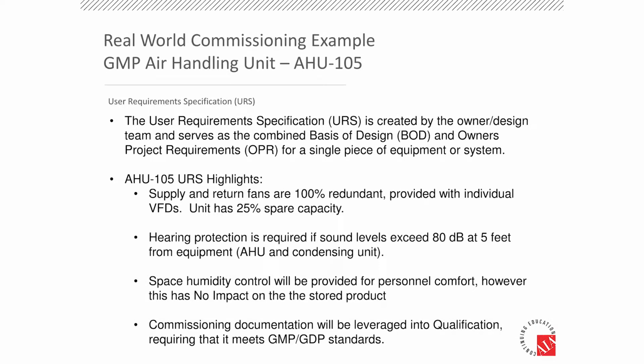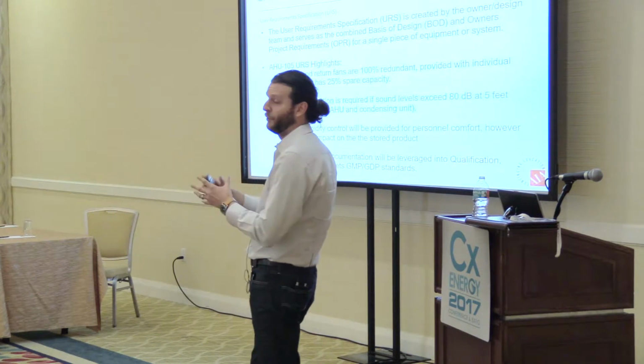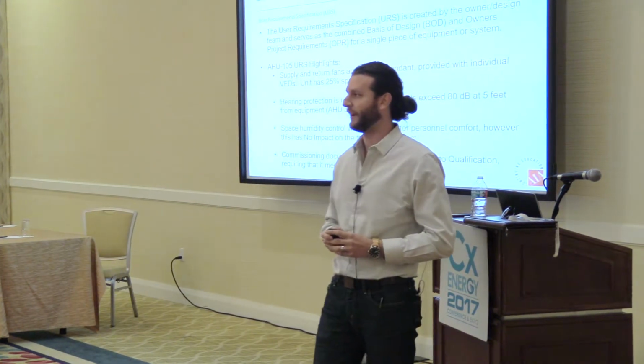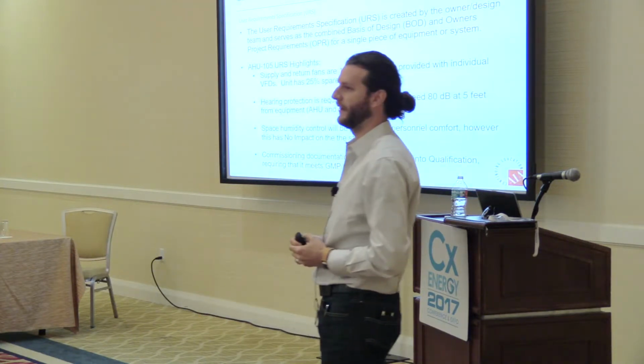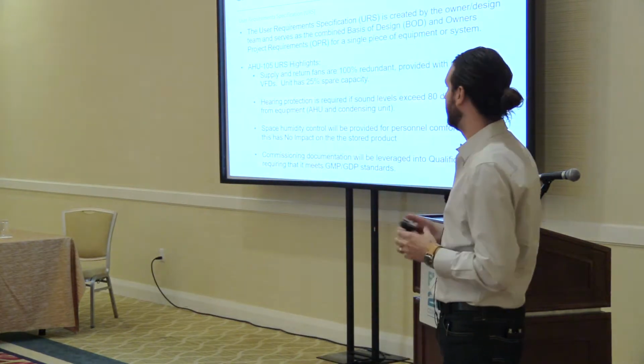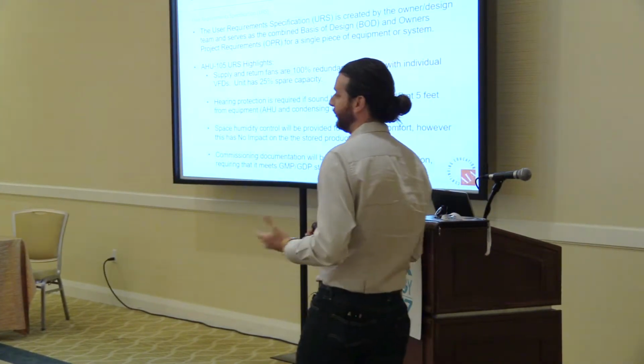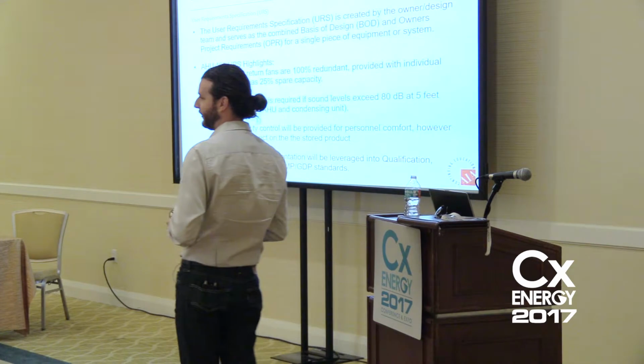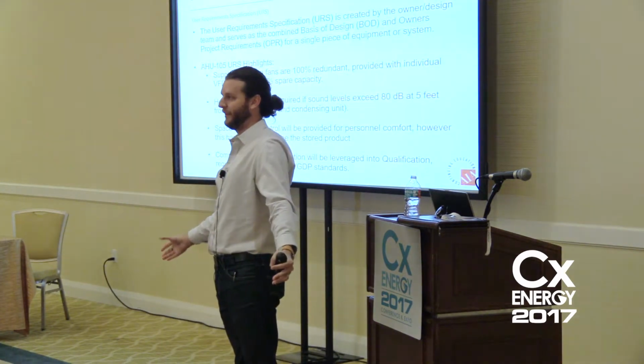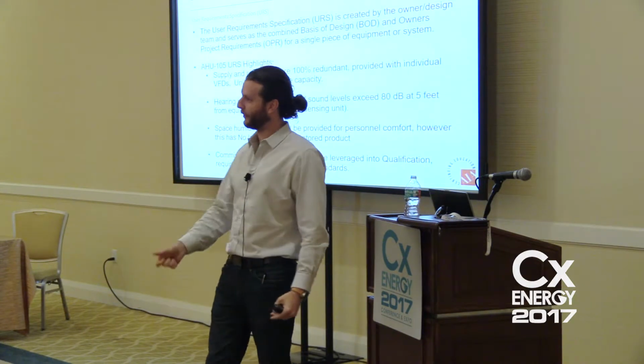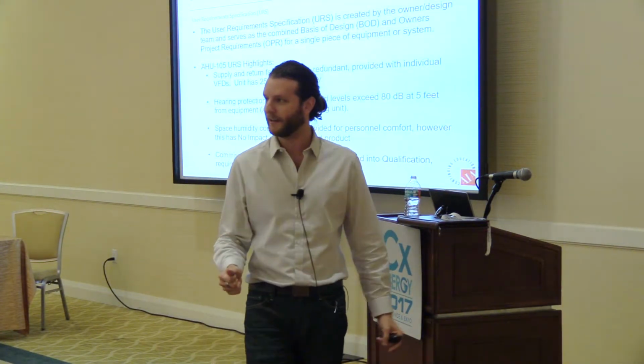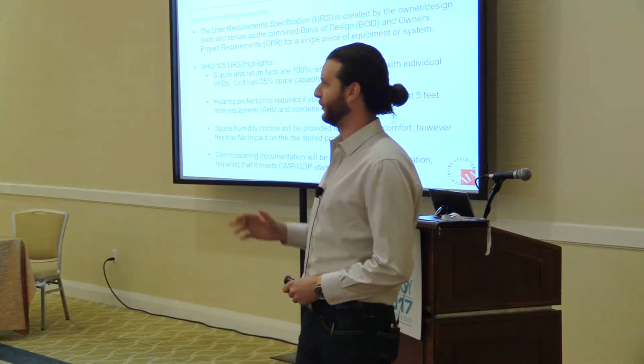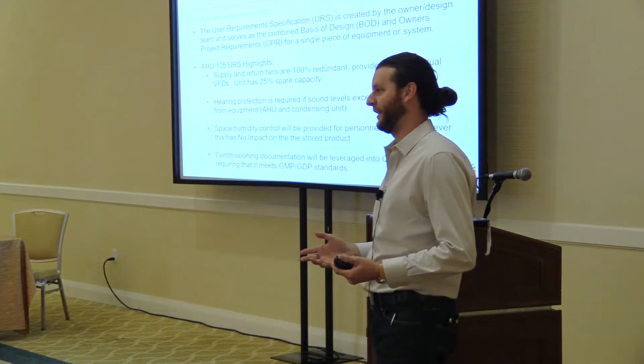Another document in this world is the URS, or User Requirement Specification. To me, the URS is like an OPR, a BOD, and a user requirement all in one document related to a piece of equipment. So you're going to get a URS for this air handling system. Some highlights: it's going to say, here's your capacity, here's some excess capacity, and here is some information from their EH&S department. They say, if it's more than 80 decibels within 5 feet of the equipment, we need hearing protection. So as a commissioning agent, they want us to go around and take sound level tests and say, okay, we're at 75 decibels, so your staff and maintenance people don't have to wear hearing protection.